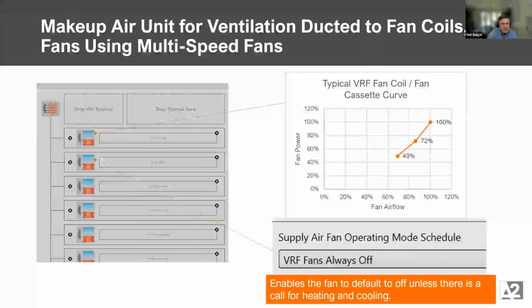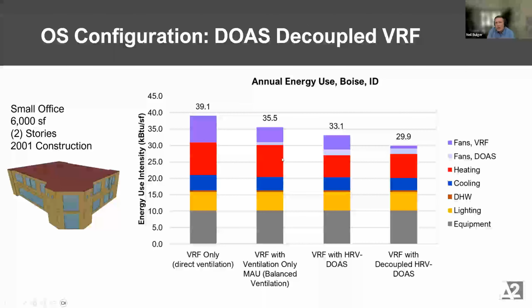And there is, I don't have a screenshot, but that is a toggle at the highest level. At the compressor level, you say, what's my COP? How do I control defrost? Do I have simultaneous heat and cooling? And so you can turn that on there. If you don't have it, it's going to look for the majority of the rooms. It's going to sacrifice the ones that are in heating when they need some. But this model did have it. So that's sort of shown in this stack to begin with.